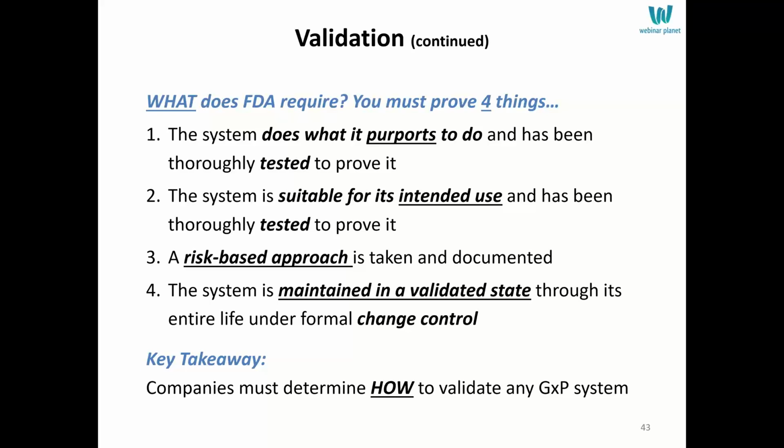You not only have to do the risk assessment for your overall system at a high level and get 1 risk rating and use that in your GXP system inventory, but then as you're going through validation, every single requirement that you define must be assessed for potential risk if the requirement's not met. And then the level of testing must match whatever the level of risk is. More risk, more testing. Less risk, less testing.